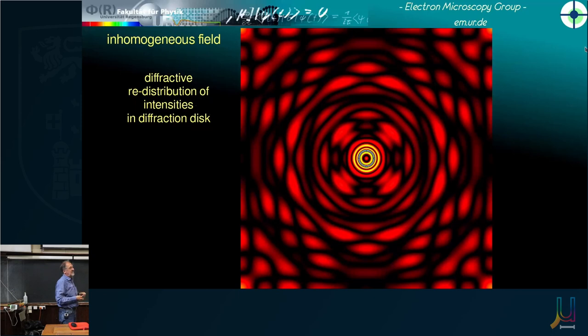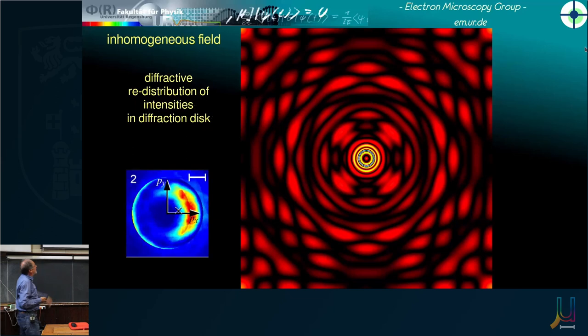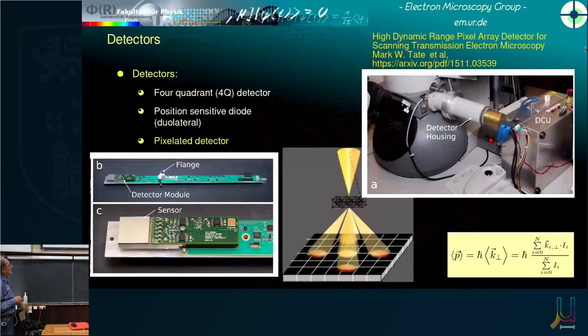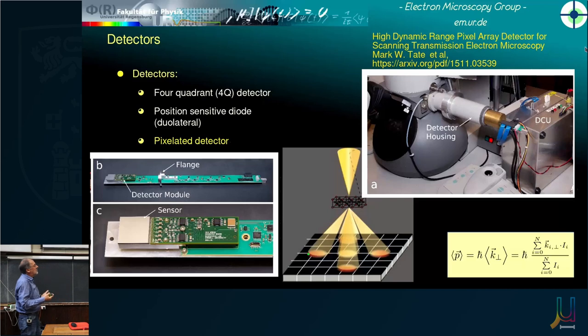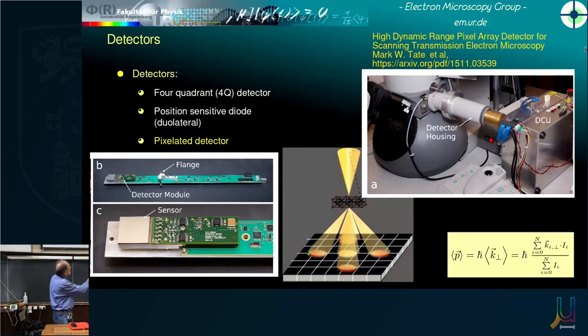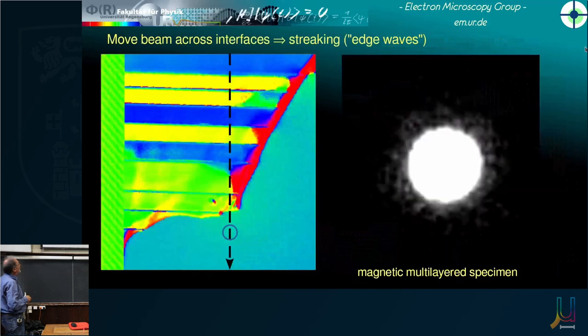A movie shows the evolution of the central diffraction disk as we approach an atomic column — this is the information we need to process, ideally viewed as a movie. The ideal detector for this type of detection is the pixelated detector — essentially a standard camera modified for direct electron beams, with slightly larger cells. It fits inside or underneath the microscope. We evaluate the center-of-mass equation to extract the information.